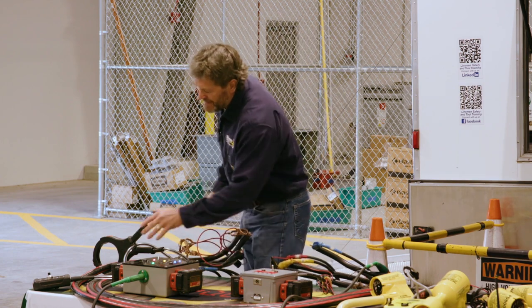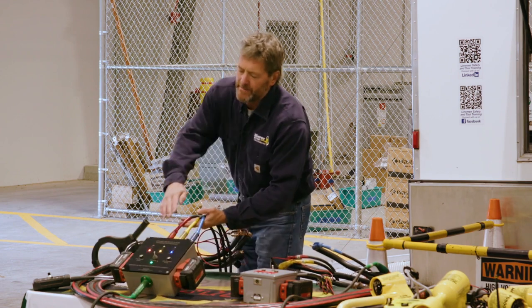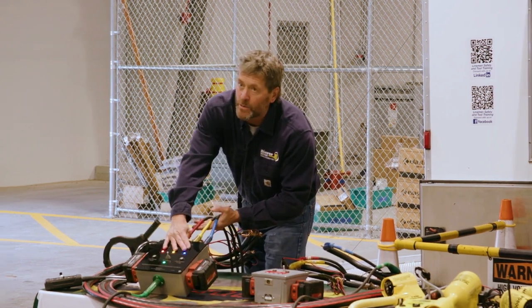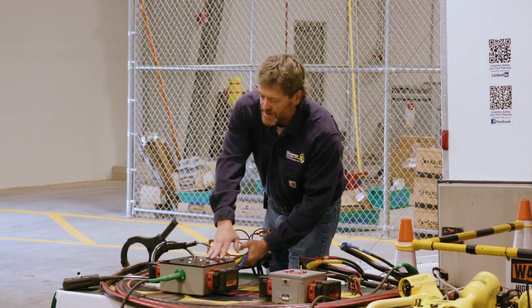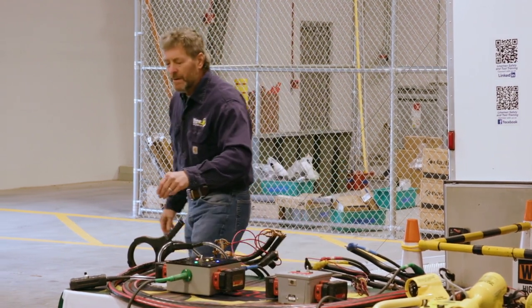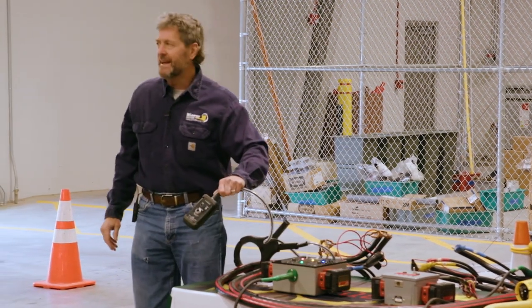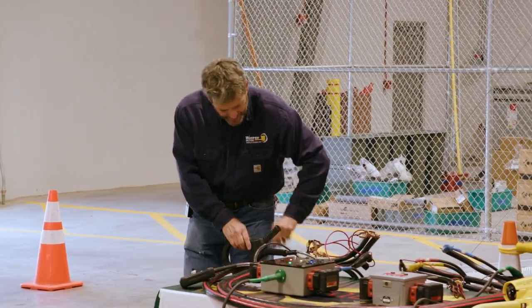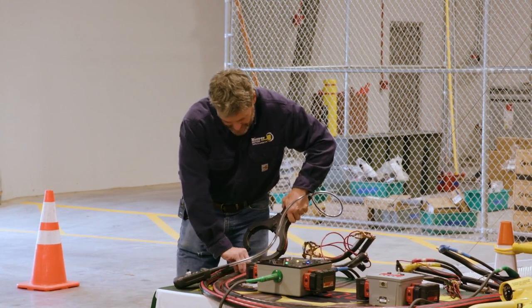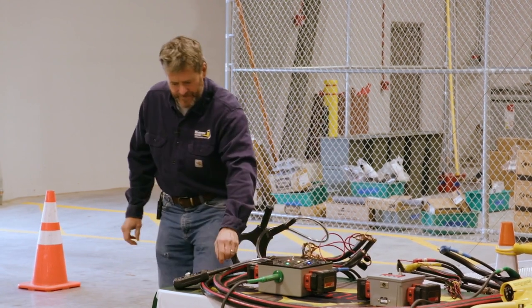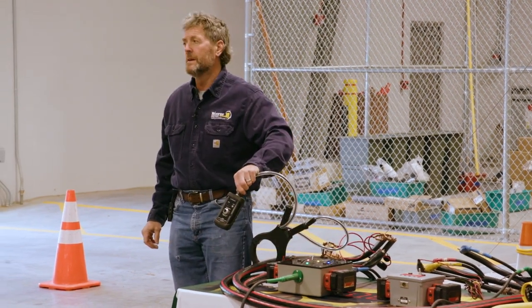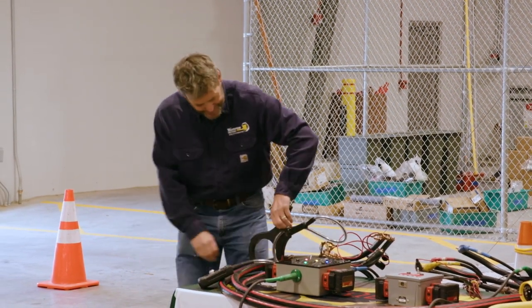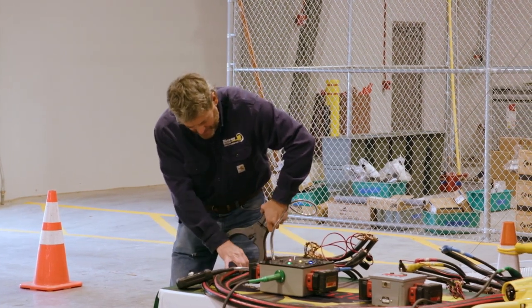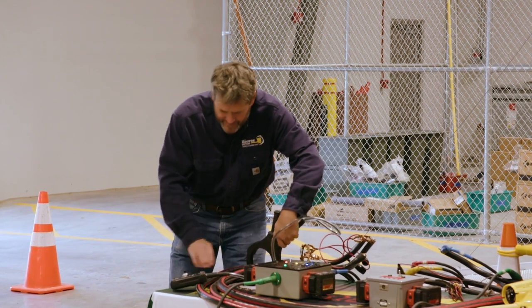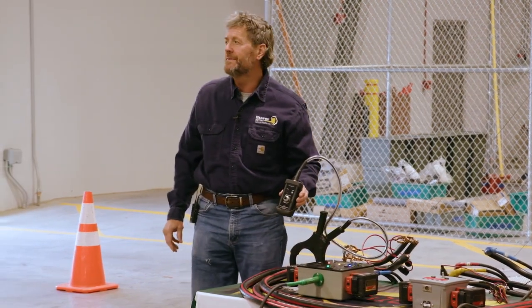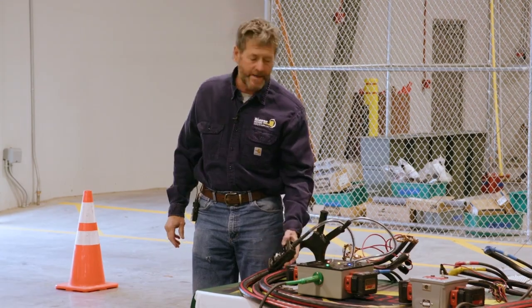All right, so we've got a CT clamp. All the lights are hot. We've got continuity, a path back to the tool through the ground. Concentrics are good. So we get one pulse here, that's A phase. Go to the next cable. Two pulses, that's B phase. And then you guys probably figured out this next one. There you go, three pulses, that's C phase. Very safe, easy to use.